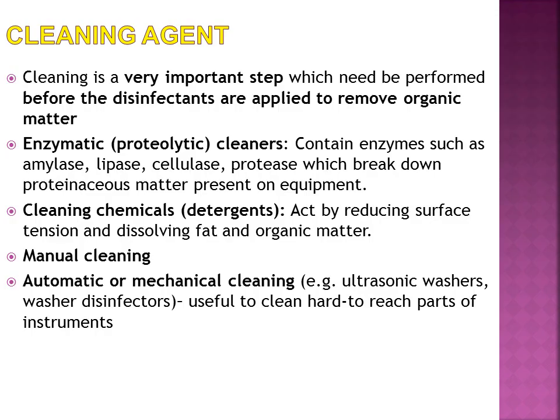Cleaning agent. Cleaning is an important step before disinfectants are applied, to remove organic matter, because a few reagents do not act in the presence of organic matter. So the examples are enzymatic cleaners. They contain enzymes like amylase, lipase and protease and all. Cleaning chemicals, so they are detergents.